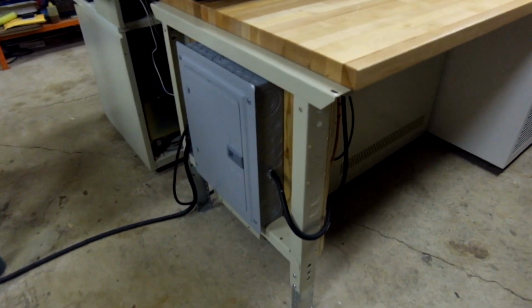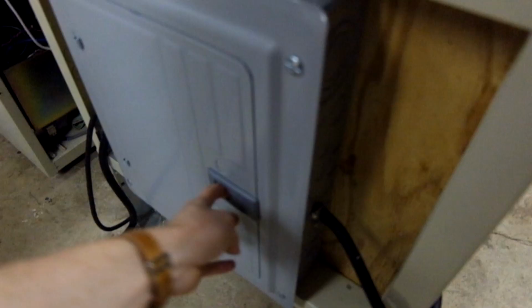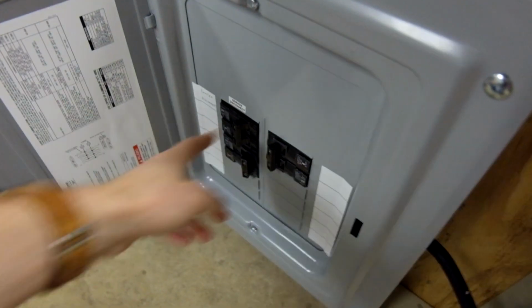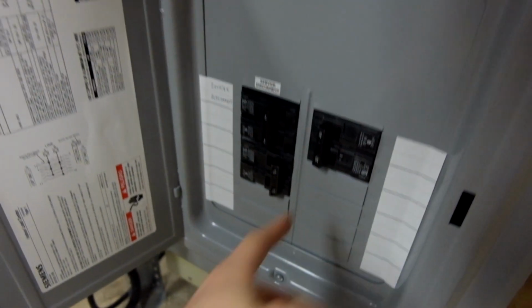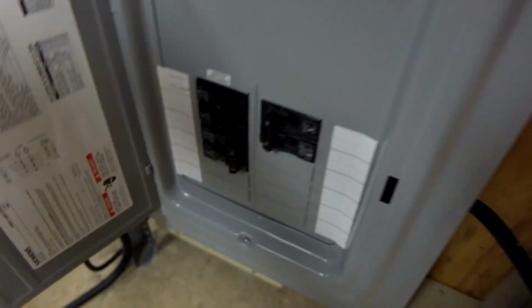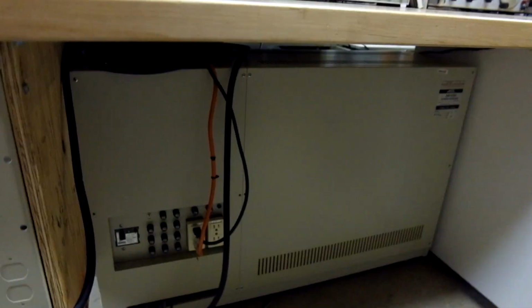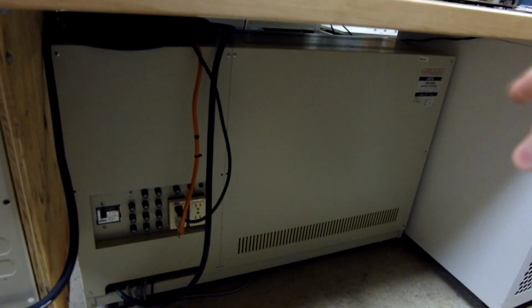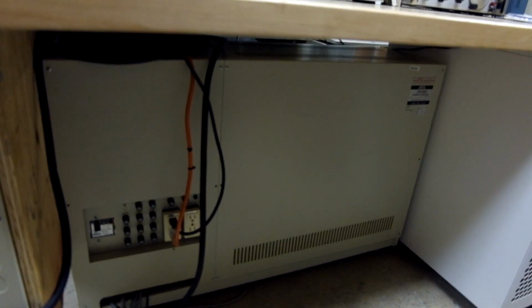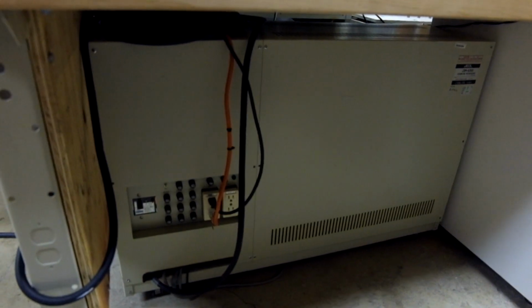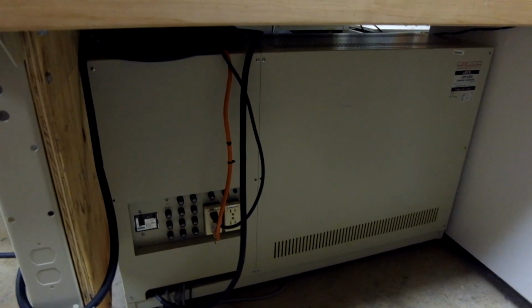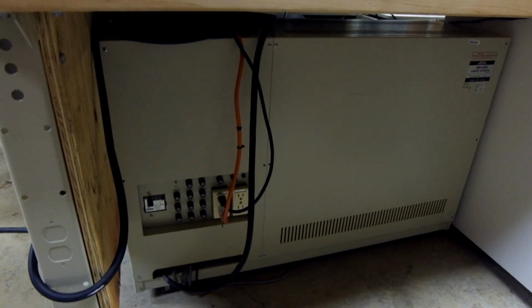So behind the microscope, under this bench here, there's an electrical panel right here, and this is a main shut-off, and then a 30-amp breaker for the microscope and a 15-amp breaker for the chiller. This is a power supply. This thing has 3 big transformers in the bottom, and I had to change the taps on this, so it takes 240 volts in and makes 200 volts and 100 volts and all the other weird power that the microscope needs. It's a Japanese machine.